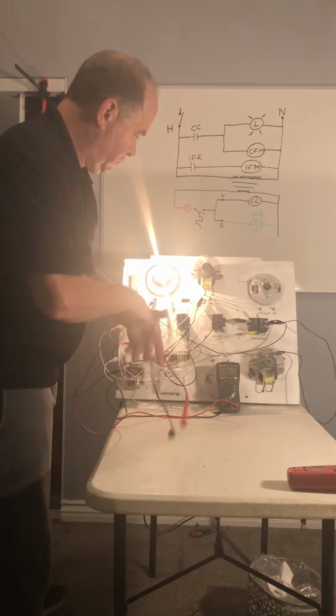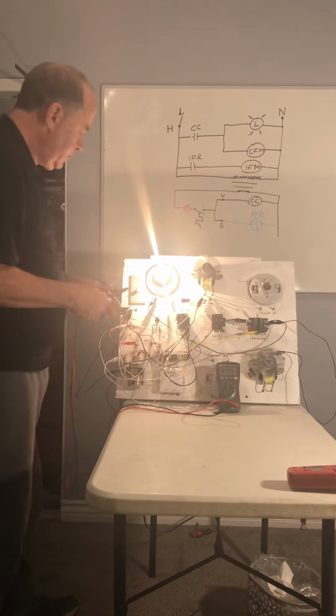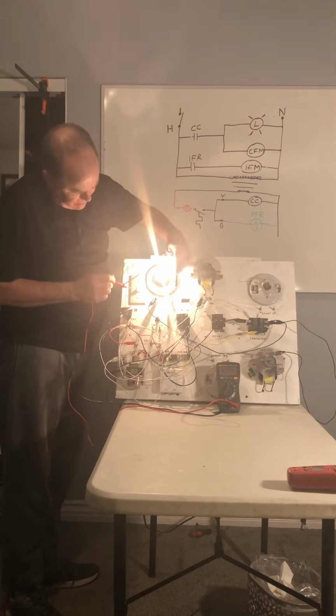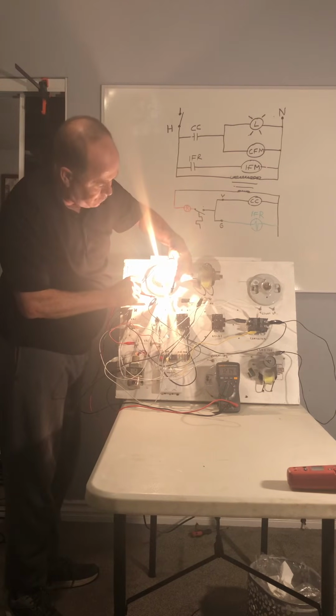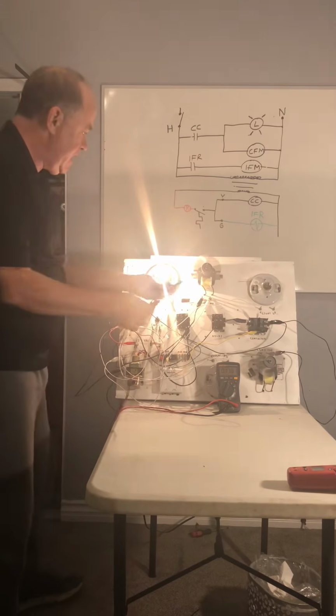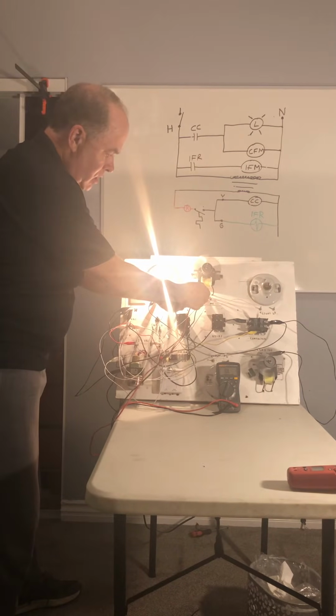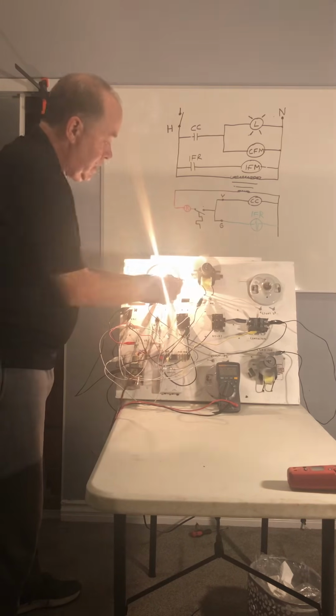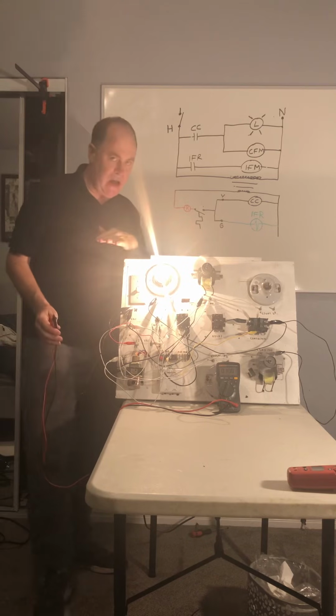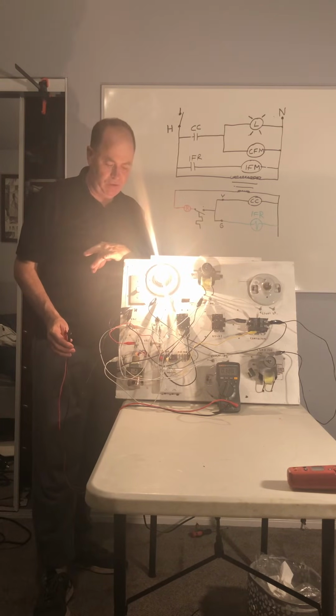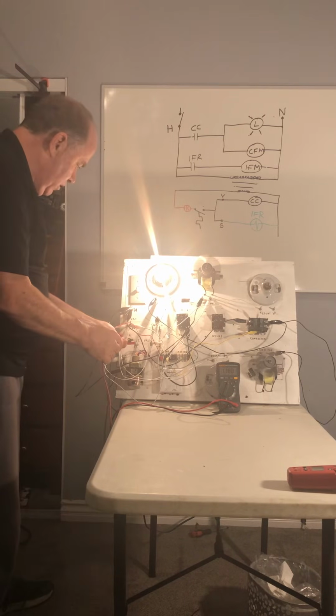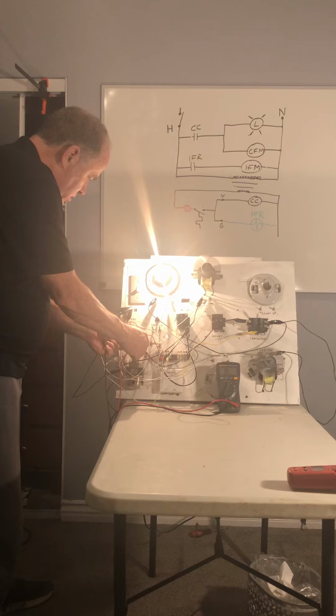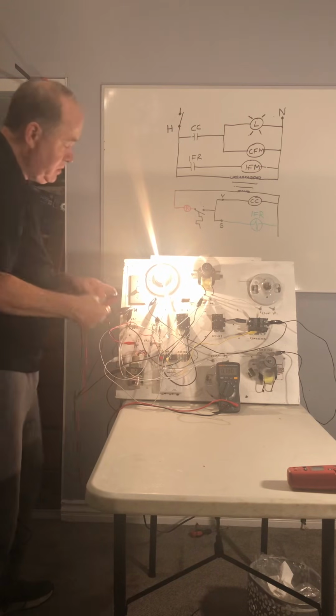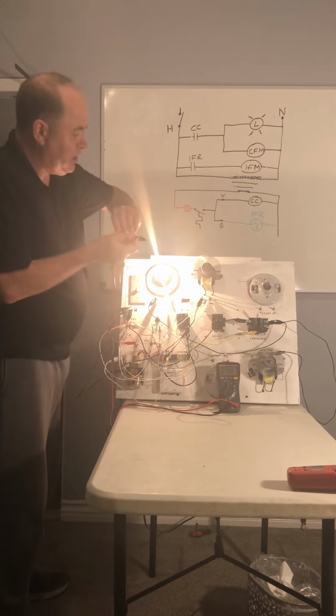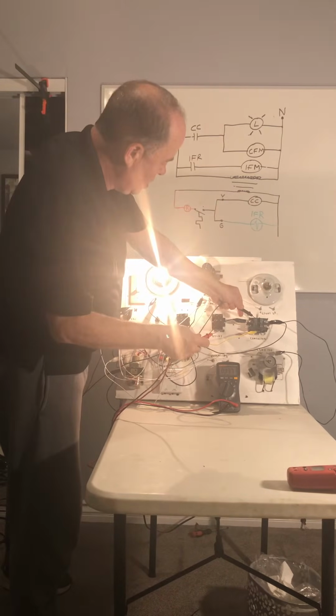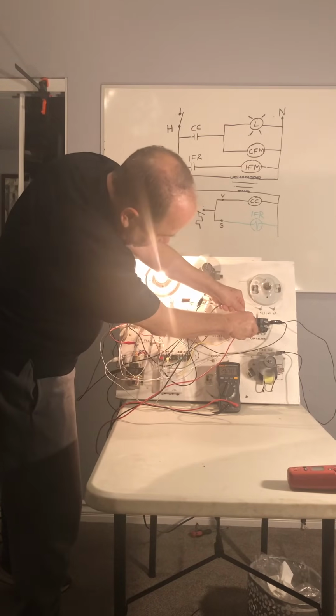Here we have to set it at volts for alternating current. And again, we're going to have 121 volts to each electrical load, whether it's a fan or a light. You see that 120. Now, the transformer is stepping down the voltage from 120 to 24 volts. So coming out of the transformer, we'll have around 24 volts, 26 volts, and you see the contacts are pulled in here, and we can check the voltage carefully and read the 24 volts here also, 26 volts.